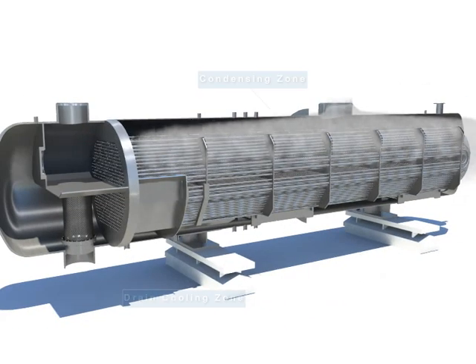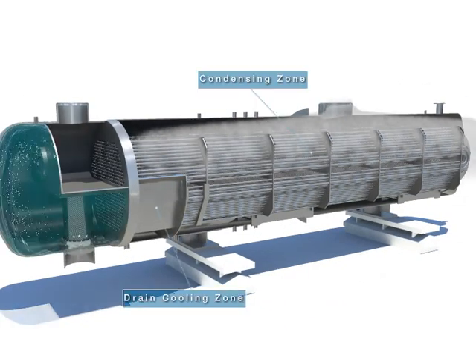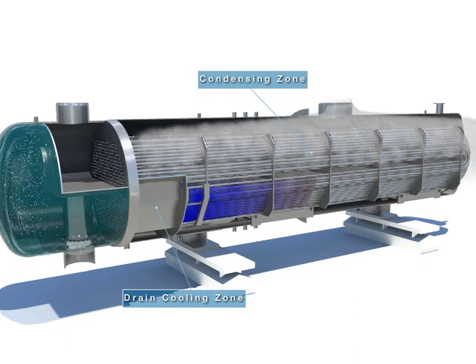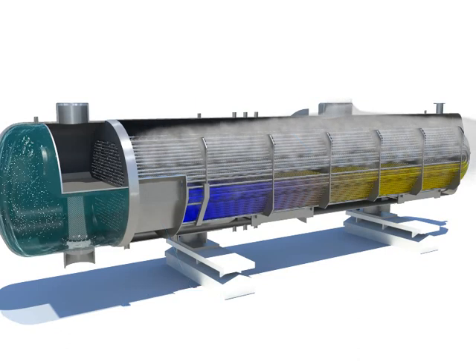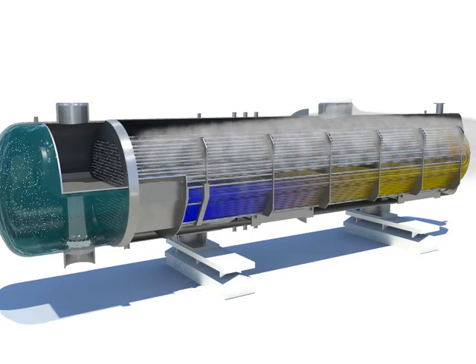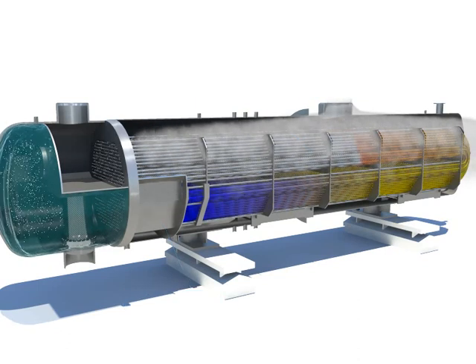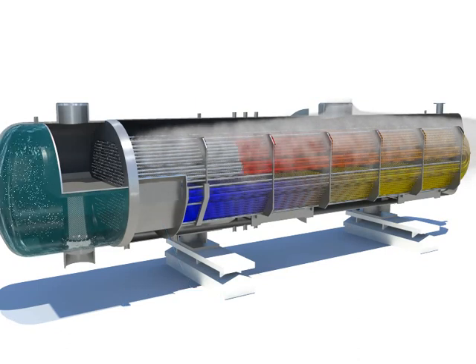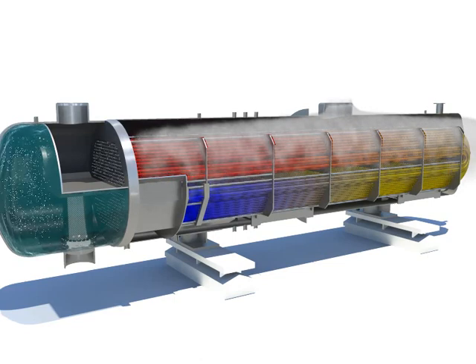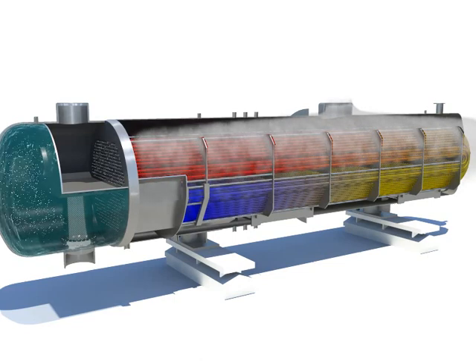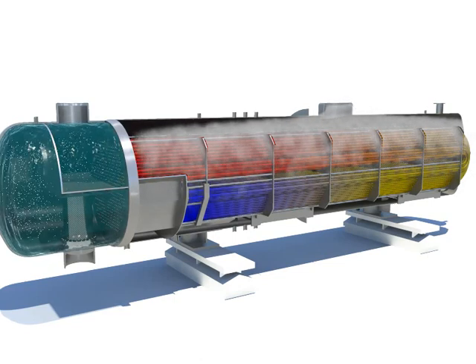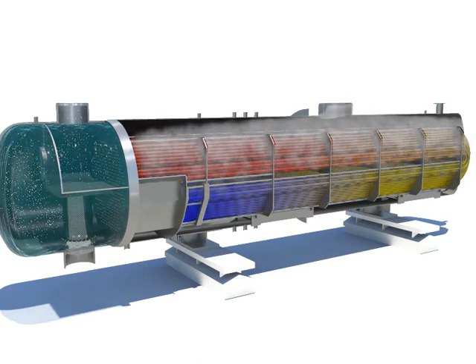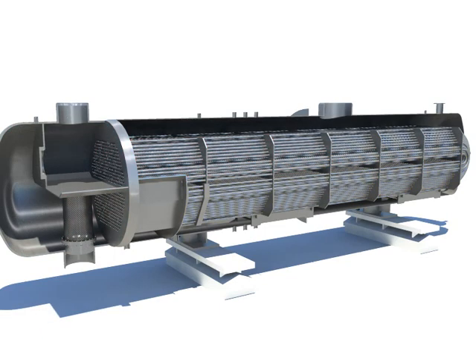The low-pressure feedwater heater consists of a drain cooling zone and a condensing zone. The drain cooling zone is located at the feedwater inlet, and the condensing zone has the largest heating area among the other heating areas of the feedwater heater.